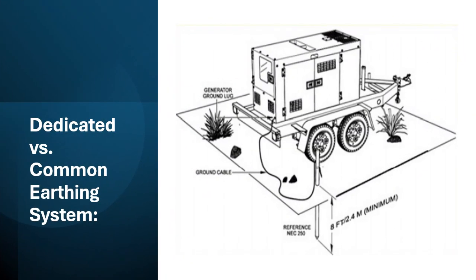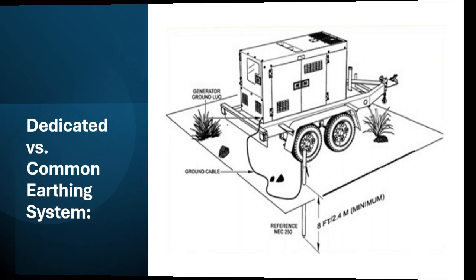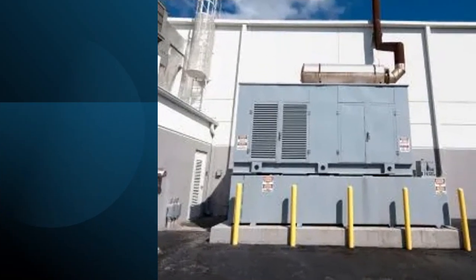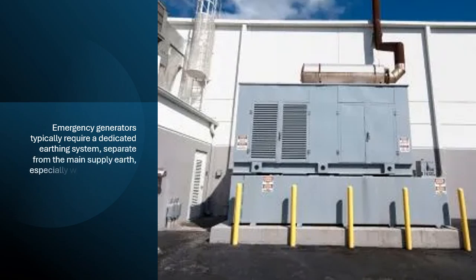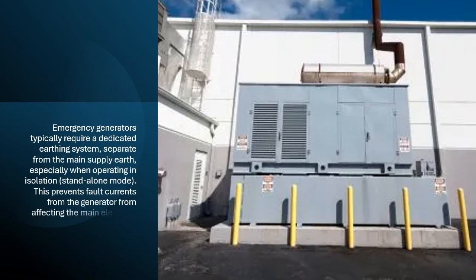Dedicated versus common earthing system. Emergency generators typically require a dedicated earthing system, separate from the main supply earth, especially when operating in isolation, standalone mode.